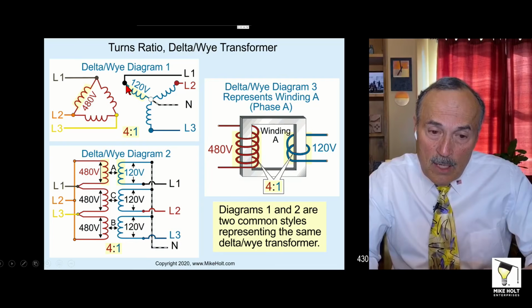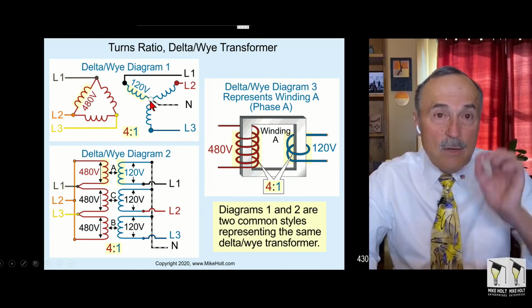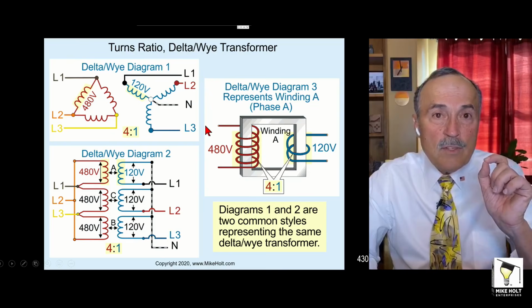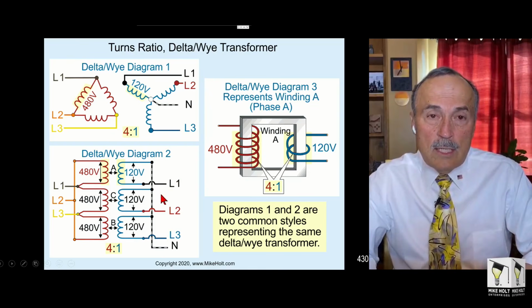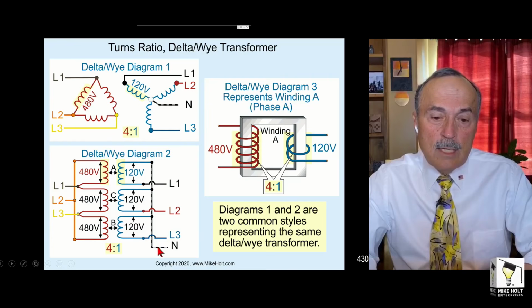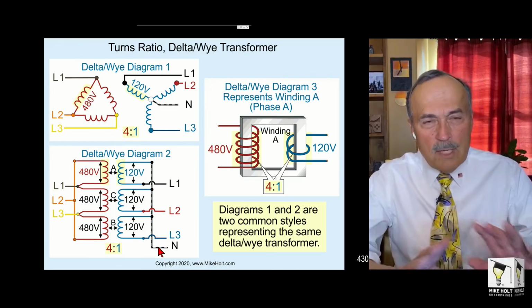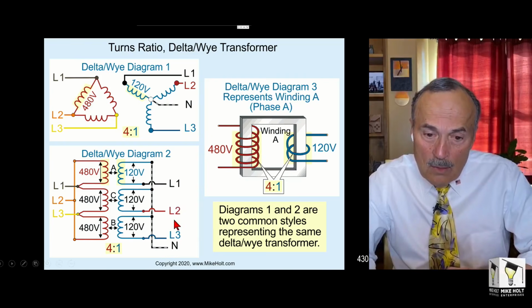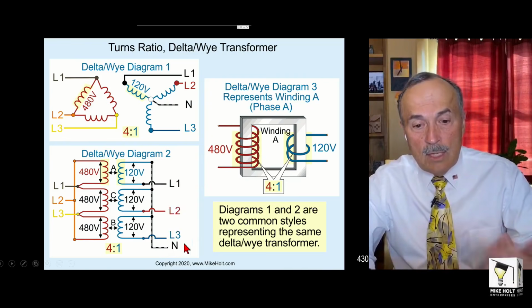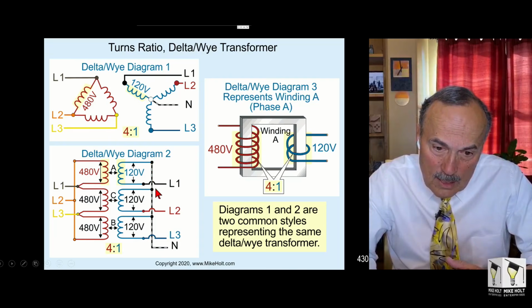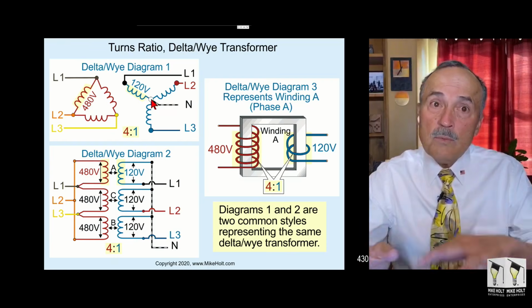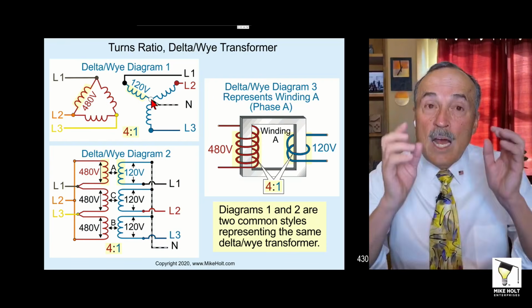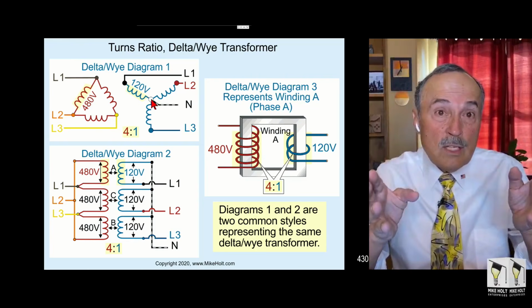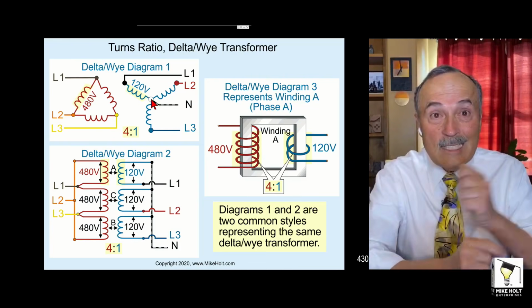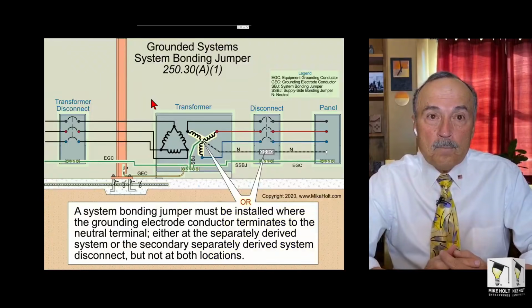And guess what they do here? If it's a Y system, then all 3 of them are connected together at one point, and the other points have different conductors connected. You're only going to see X1, X2, X3, and probably X0. They're not always universal, but that's a pretty common way. So now you're bringing in line 1, line 2, line 3, and coming out with a neutral. But look, this is connected to this one, which is connected to that one, which is right there. I don't have time to spend more time on this. We covered that in theory, but I at least wanted to give you an idea that a 3-phase transformer is 3 separate physical single-phase transformers that are just connected together. All right. Okay, you have a question real quick?